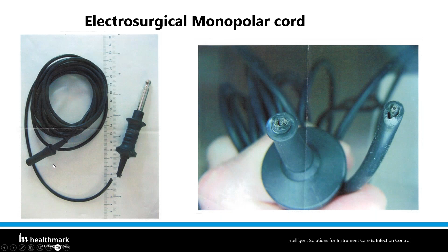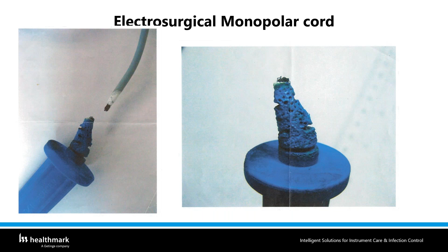And I'm going to show you a couple of FDA MAUDE database entries. It said that for the monopolar cord, there were 4 additional reports just in 2020 involving surgical fires. So what happened is that the cord, obviously this end of it is heavy. Over time, the inside starts breaking, the wires start breaking. At some point, you don't have enough wire. So in this case, what happened is that the surgeon usually sets the dial to 25 or 30 watts. However, if you have some issue with these wires, maybe some of the electricity does not return to the machine. So the surgeon asks to increase the wattage to 35, 40, and 45. At the 45 level, this is what happened. The energy basically broke this off, and the cord fell to the ground, and this was obviously still attached to the machine.